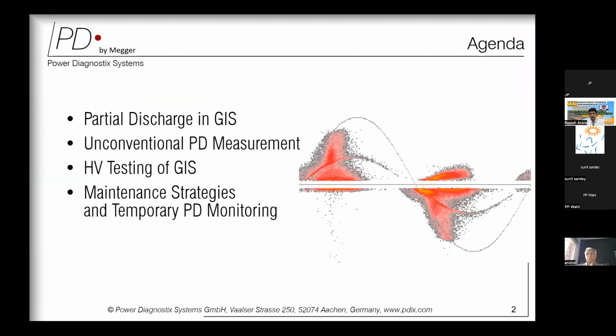If we talk about partial discharge, let me first go through the agenda. What is our agenda of today's presentation? We would be touching upon the topics of partial discharge in GIS, a little bit about the basics of partial discharge in GIS, and the unconventional partial discharge measurement technique used for PD measurement in GIS. We will touch on the topic of sensitivity and high voltage testing, which are the standard commissioning tests associated with GIS, and then the maintenance strategies and temporary monitoring facilities, or the functionalities used to analyze and diagnose partial discharge, and then take actions to rectify and increase the reliability of gas insulated substations.